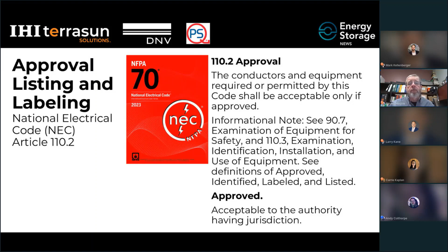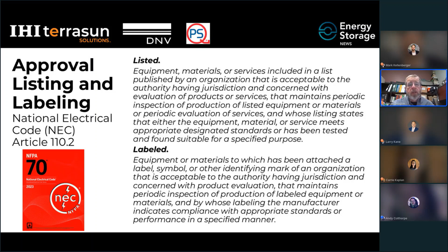Listing and labeling is the terminology most used, rather than the word approved, for equipment in the US. Listing means that when a certification organization reviews a product and certifies it, that product is included in a public list, so anyone can check that it was actually reviewed and listed by the certification organization. Labeling is done after the listing is complete, and is done by the manufacturer in most cases, once the certification organization allows the label to be put on. The certification organizations that do this for the US are most commonly called NRTLs, Nationally Recognized Testing Laboratories, and they're who would be doing this listing and labeling.